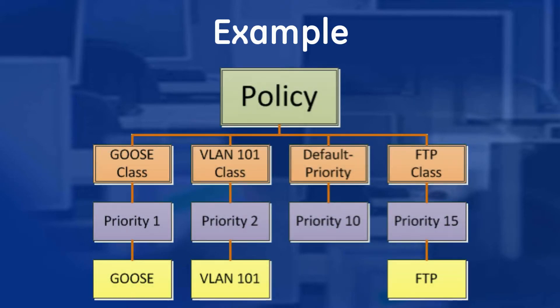Now that we have a basic understanding of how QoS works on the Orbit MCR900, let's look at a more specific example. Let's say that a user wants to prioritize a specific ether type above all other LAN traffic. In this case, the ether type is Goose. Then the next priority traffic they want is all traffic on VLAN 101. Let's say they also want to give a low priority to FTP traffic. Lastly, all remaining traffic that does not match any of the provisioned classifier needs a priority as well. This is called the default priority and must be set.